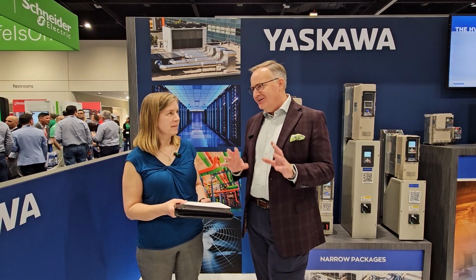Okay. So with respect to the new R454B refrigerant, and from a technology and safety standpoint, what are the latest electronic advancements? What do you use with regard to mildly flammable refrigerants? Yeah, so the industry was required to transition to these lower GWP refrigerants beginning January 1st of this year. So when we did that, all these new refrigerants are now in this new category known as A2L. It's a mildly flammable refrigerant. Now, it sounds scarier than it really is. Most of the refrigerants we were using before were technically kind of flammable too. So it's really not too different.